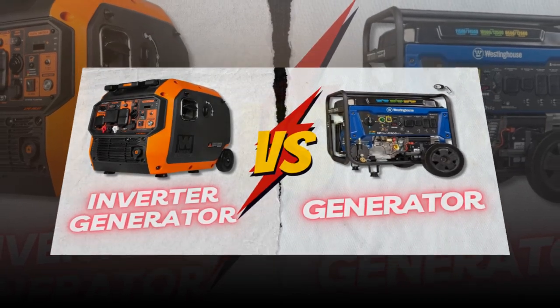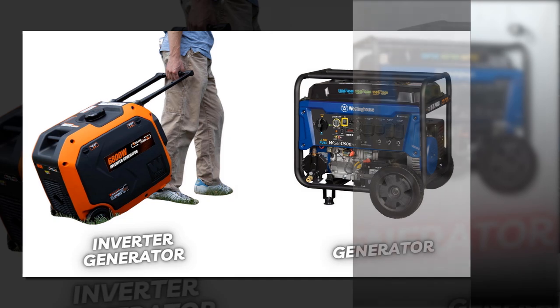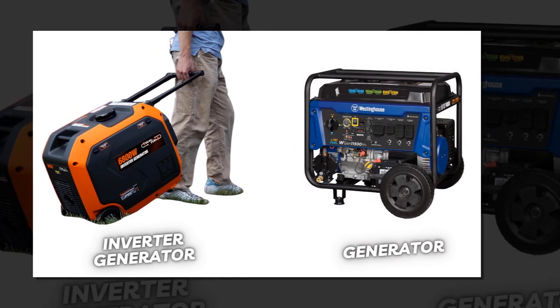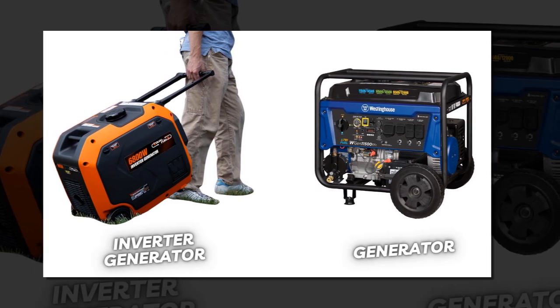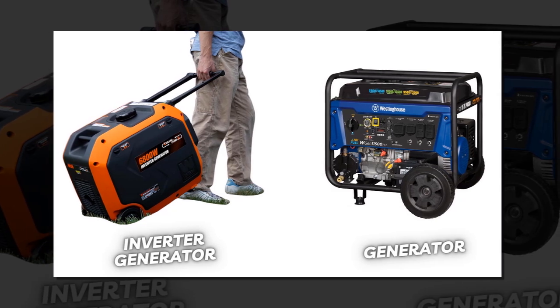Let's start with power quality. That sounds critical, especially now. It's hugely important. With traditional generators, the power they output is often called dirty. Dirty power. What does that mean? It means the electrical wave isn't a smooth, perfect sine wave. It has fluctuations, distortions. We measure this with something called total harmonic distortion, or THD.